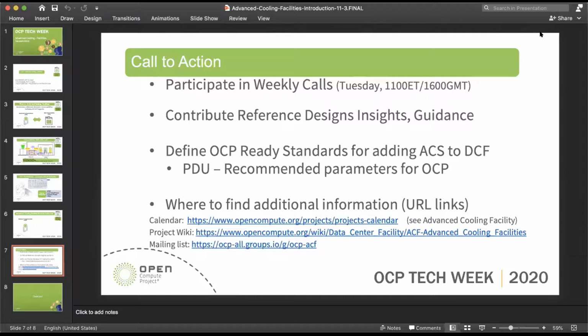It's a different philosophy we're finding if you talk to rear door heat exchangers versus cold plate versus immersion. Can we find a harmonization that lines up with all three, or at least a matrix, so that if a data center owner sees they're going to add any of those three in the future, they may want to set up for one place. If they decide their only future is, say, cold plate or immersion, they may want to take a different approach.